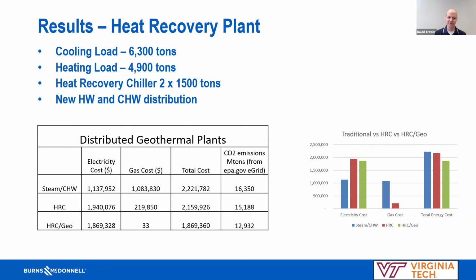And this is the result of this one. Heat recovery chillers alone, they save a significant amount of scope 1 emissions, about 80%. But when you look at scope 1 and 2, there's a smaller savings. That's mainly because the grid in this area isn't as clean as other areas in the country. But still, it's a pretty significant impact in scope 1 emissions. Now, I went ahead and ran a geothermal scenario, and at that point, we almost completely eliminate the gas usage in this area of campus. The cost goes down, but still not as significantly as the other areas of campus, and carbon emissions go down again.